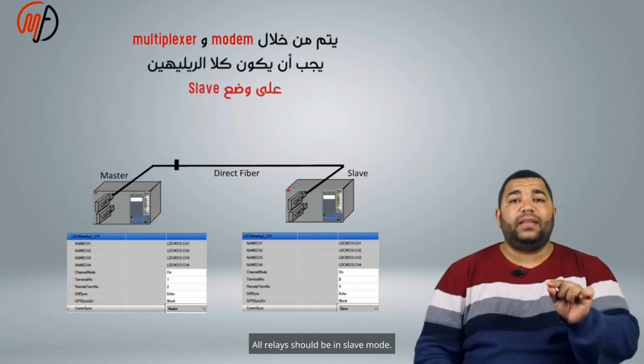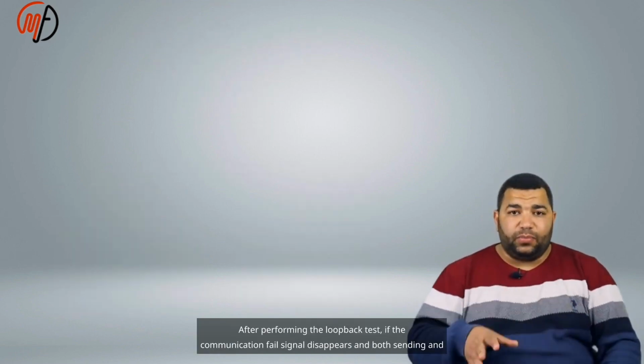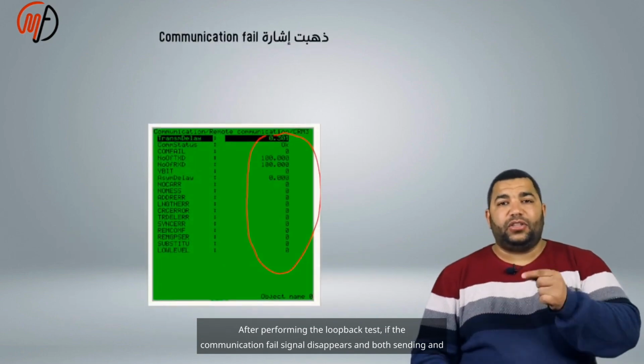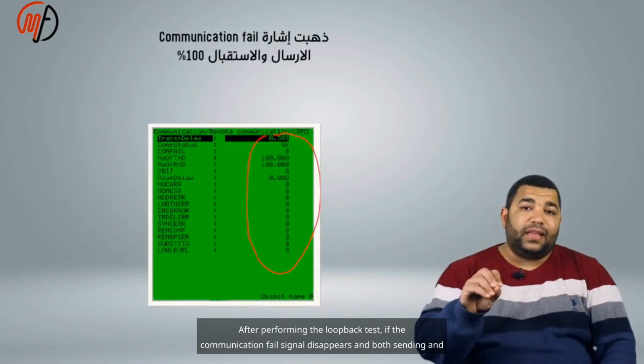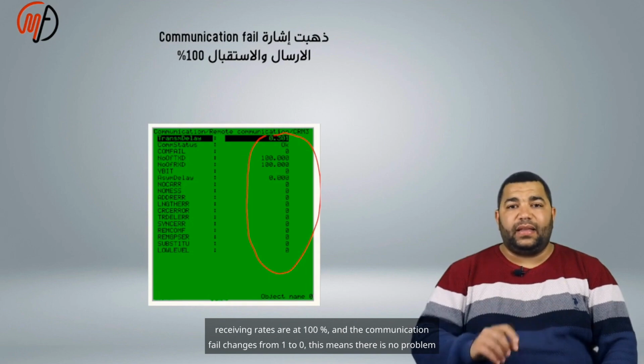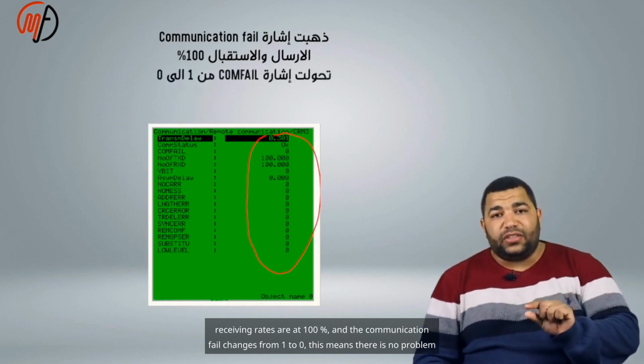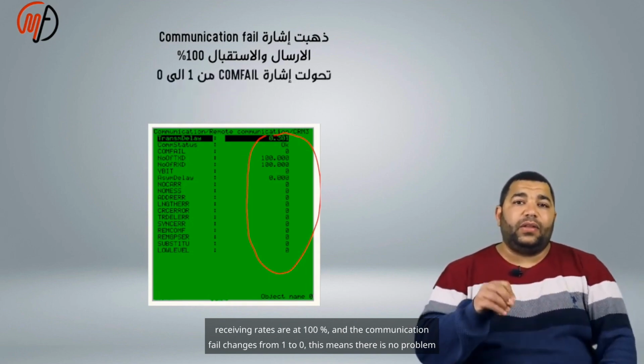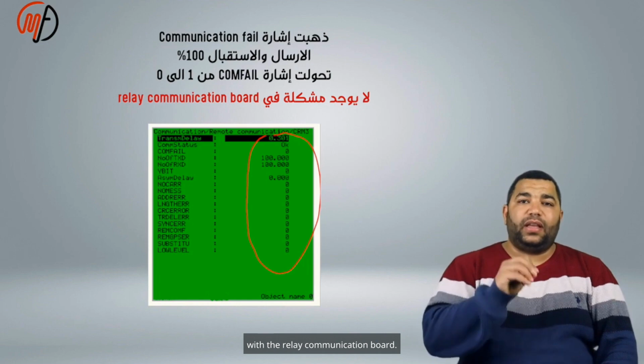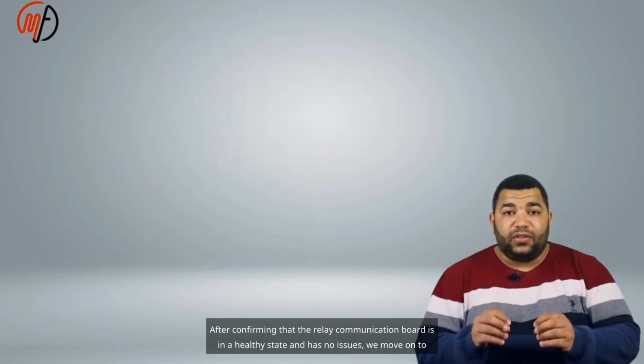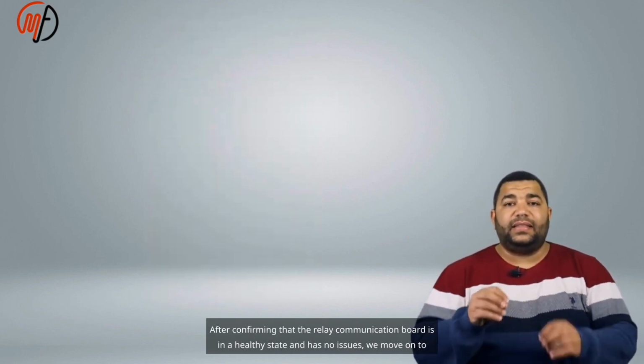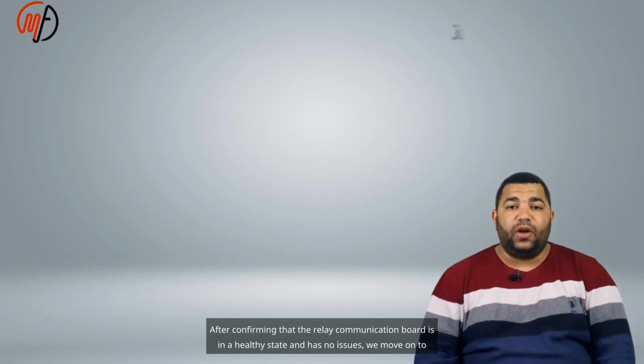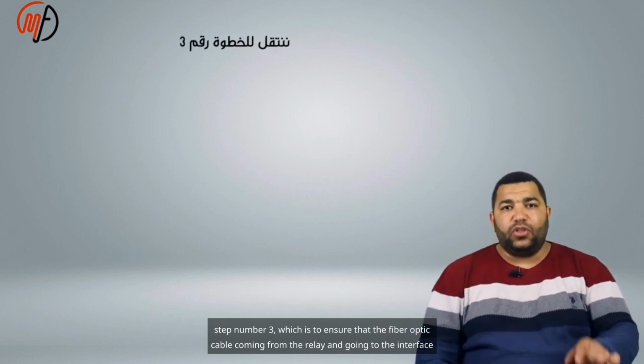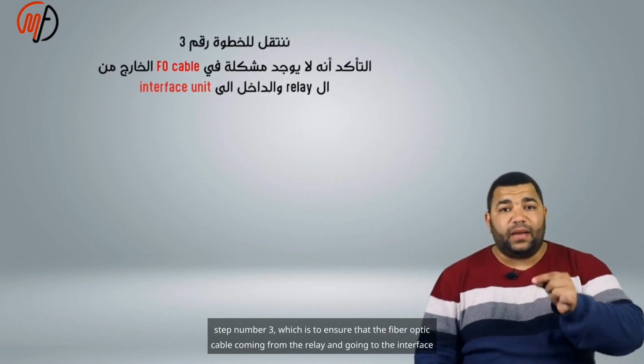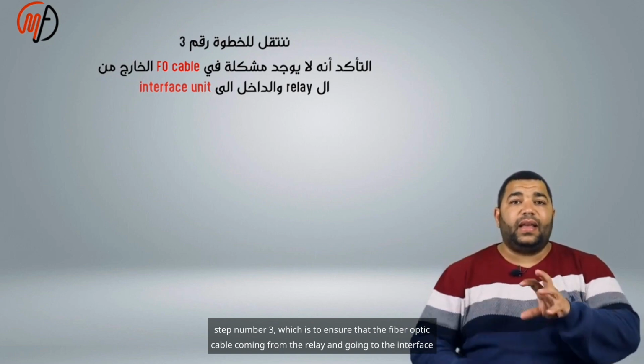All relays should be in slave mode. After performing the loopback test, if the communication fail signal disappears and both sending and receiving rates are at 100% and the communication fail changes from 1 to 0, this means there is no problem with the relay communication board. After confirming that the relay communication board is in a healthy state and has no issues, we move on to step number 3, which is to ensure that the fiber optic cable coming from the relay and going to the interface unit has no problems.